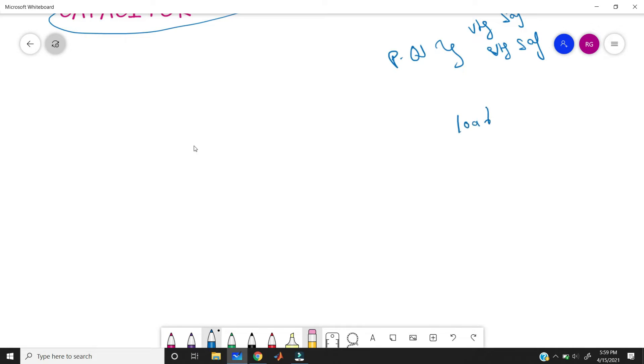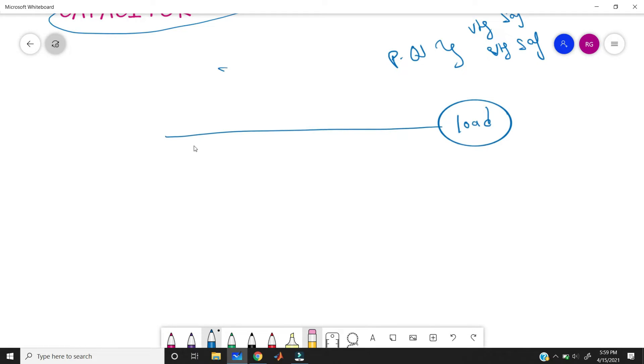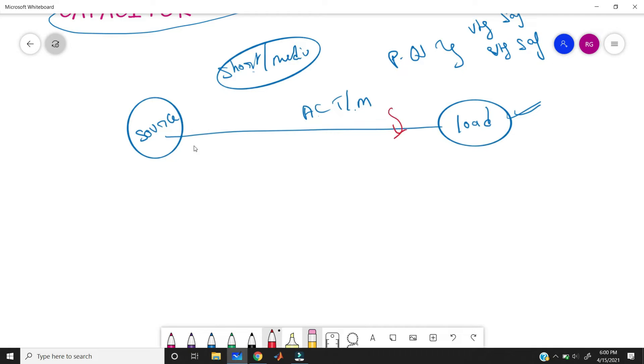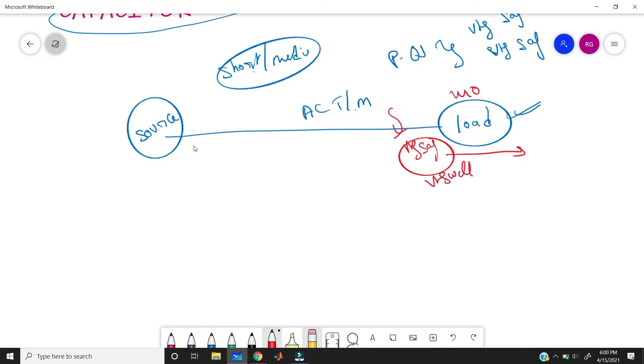Distribution level means it is nearer to the load, like a short or medium transmission line. In short and medium transmission lines we use an AC transmission line only, because this is the distribution point. So here we take the source and the load on the AC transmission line. At any situation it is possible to get a fault like voltage sag or voltage swell. For example, if we need to give 240 volts to the load but due to some fault we are only getting 200 volts, that is the fault condition. To eliminate this we need to inject another 40 volts to maintain the required load voltage.